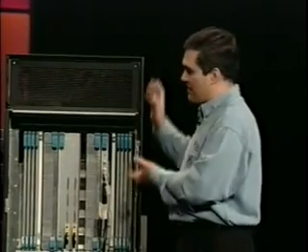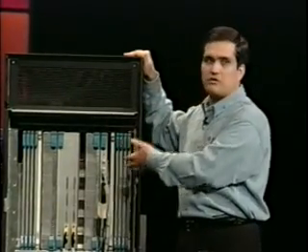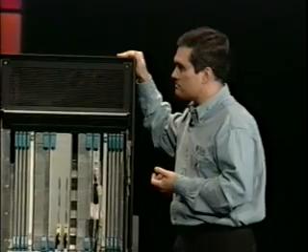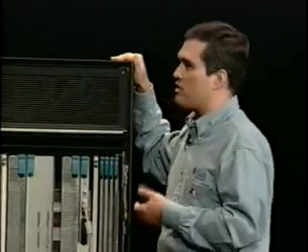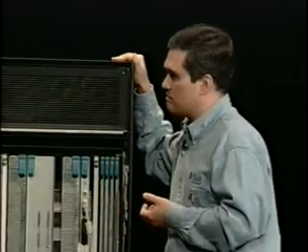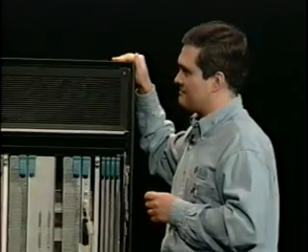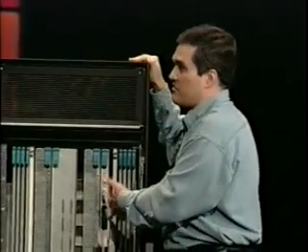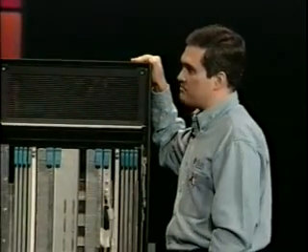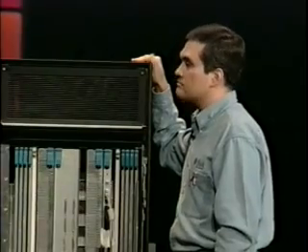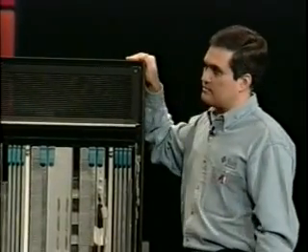Because we don't have redundancy on these critical components, if I simulate the failure of any component here, you'll see that the server will fail. If you remove any board here, the entire system comes down. If, for instance, I take a memory board and remove it, the system would just go down. CPU board? Yeah, if it fails, the system goes down. How about a control board, something as simple as that? Yeah, even the control board that contains the clock of the system, if that thing fails, you have the system go down. So we're talking about a $5 component that can bring down an entire mission-critical application.